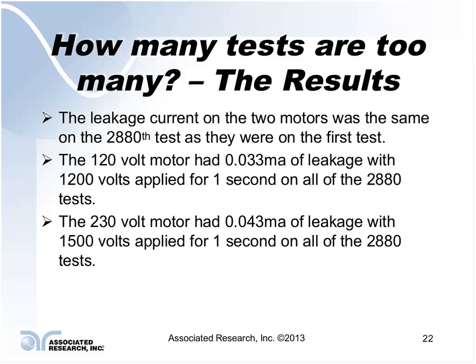They were rejecting items that weren't really failures. One of the things I did determine was that the motors that did fail were, in fact, failures. They had insulation that was not properly inserted within the product itself.